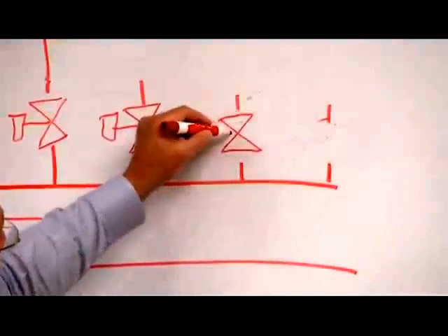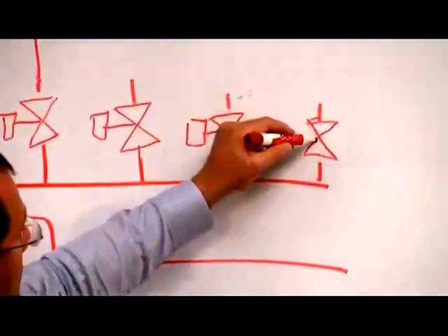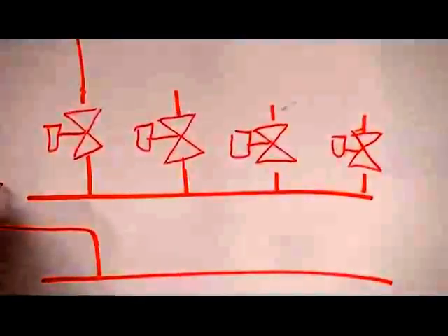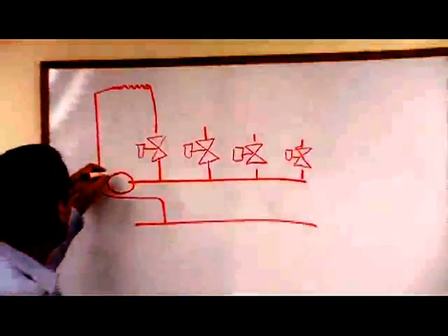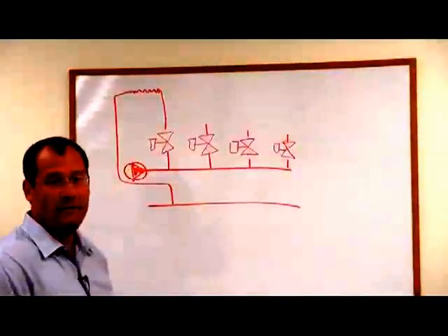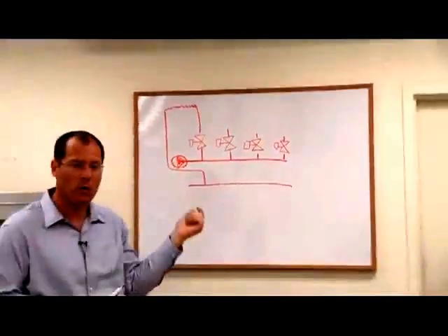And each of the thermostats, now all they do is open up this zone valve and let flow off to the heating zone. And we install one pump that is able to vary its speed. It speeds up and slows down based on the amount of work it has to do.